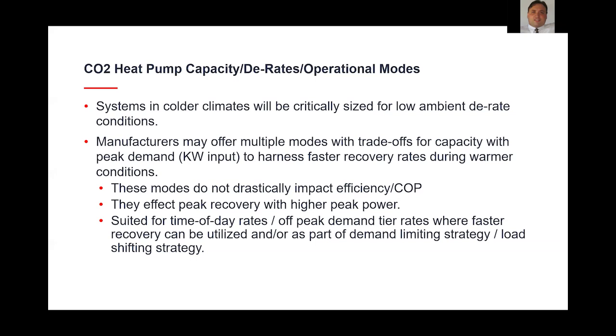All right, so CO2 heat pump capacity, derates, operational modes. Systems in colder climates, and this is pretty obvious, I think, are going to have to be critically sized for those low ambient conditions. So that's what we're fighting. Just like with any heat pump, as we move into more northern climates, we're sizing critically for these derated capacities.